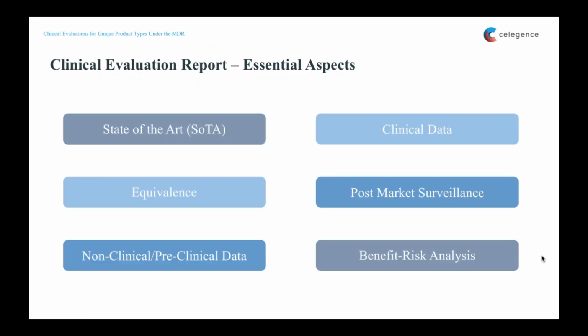Non-clinical or preclinical data, like the usability and human factor evaluation studies, are also important sources of information to substantiate performance where they can be leveraged. Once again, validation to standards or other performance testing, bench testing, needs to be linked to the actual clinical performance or the state-of-the-art requirements from the particular device or device family when the data is being analyzed. This is something that notified body observations tend to highlight: the gap between information presented and its meaning in terms of demonstrating safety and performance.